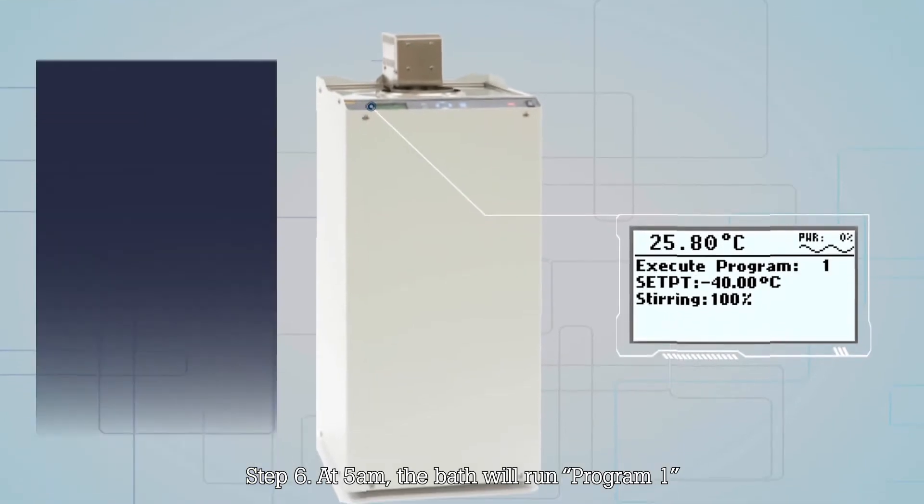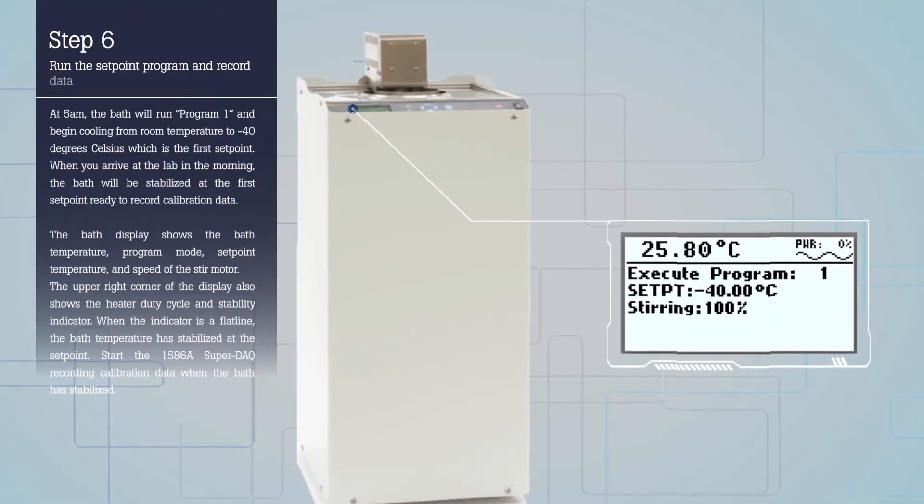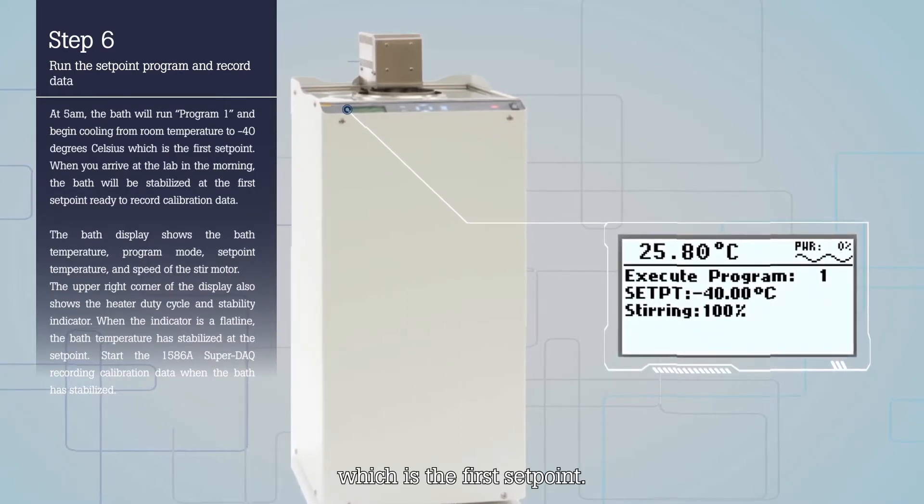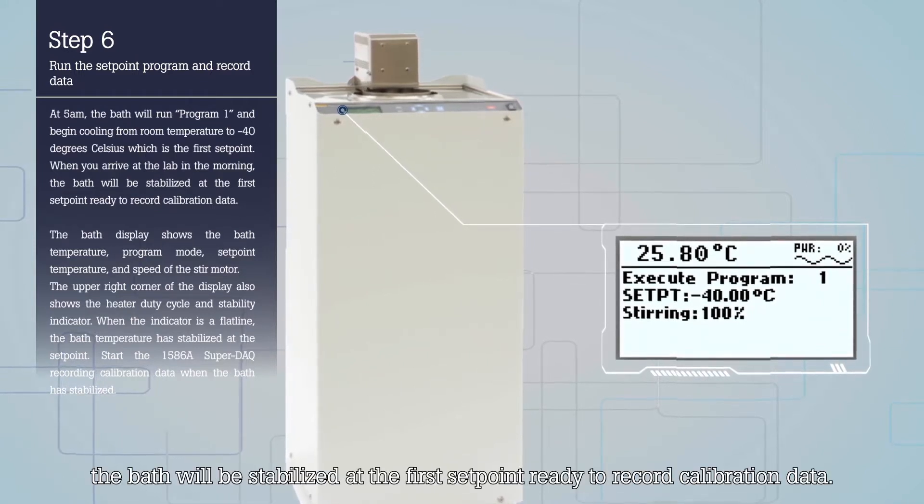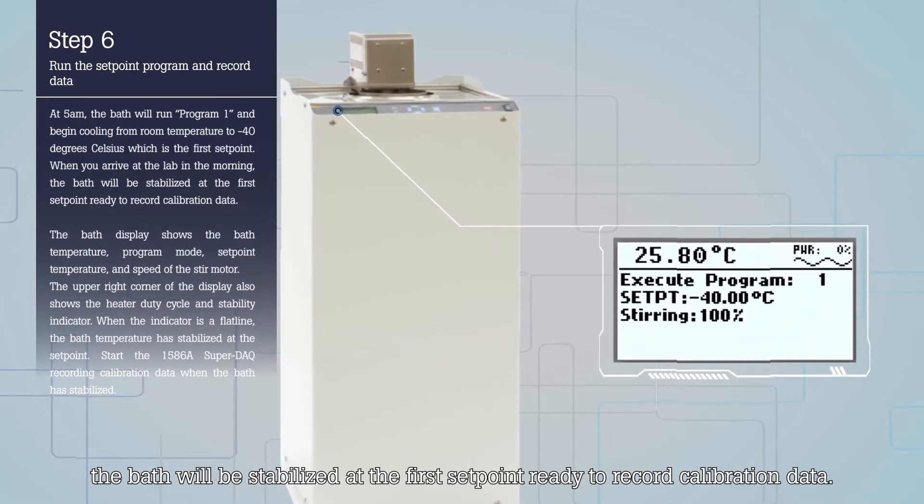Step 6. At 5 a.m. the bath will run Program 1 and begin cooling from room temperature to minus 40 degrees Celsius, which is the first set point. When you arrive at the lab in the morning, the bath will be stabilized at the first set point ready to record calibration data.